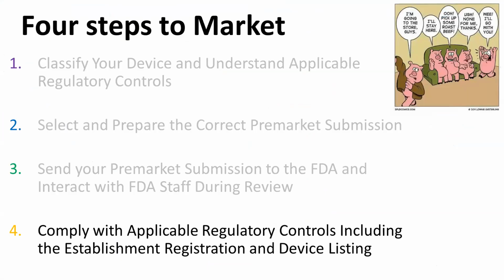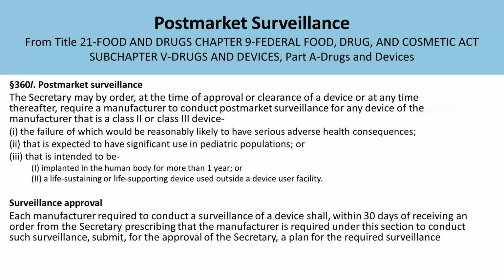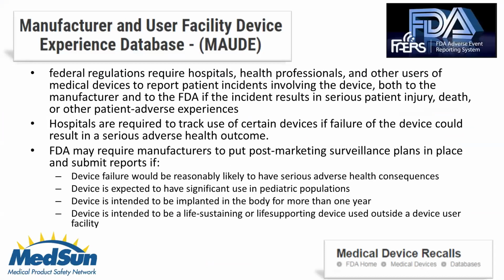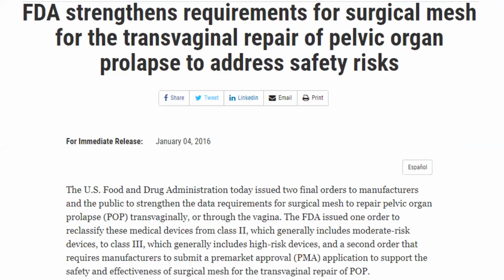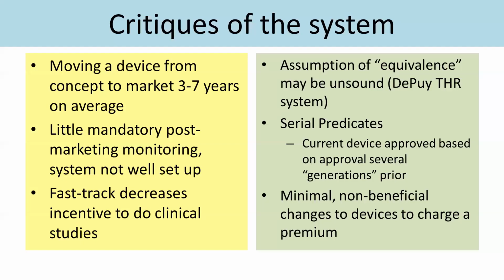So finally, once you're approved, you have to comply with regulatory surveillance, which is post-market. Unfortunately, it mostly is adverse events. There isn't a lot of ongoing surveillance of how devices are doing and if they're working well. But there are regulations that you have to report if there's serious failures. For example, we saw this with some of the gynecologic meshes. The system isn't perfect. The mandatory post-marketing is not really well set up to capture all adverse events.